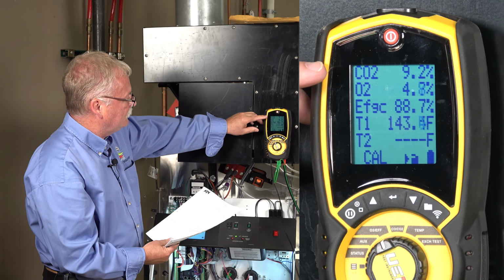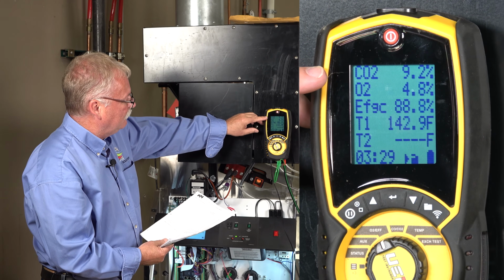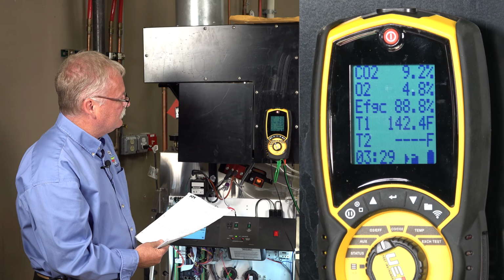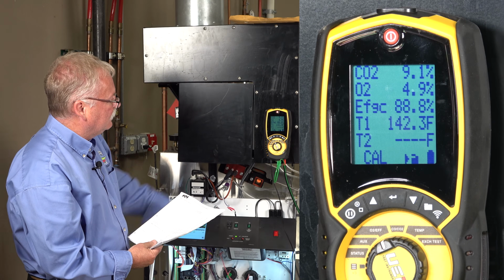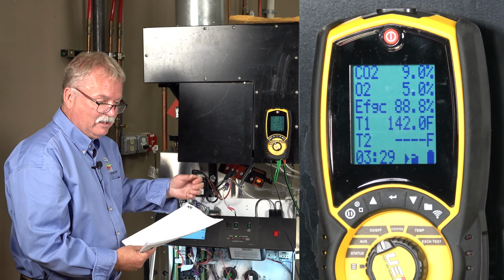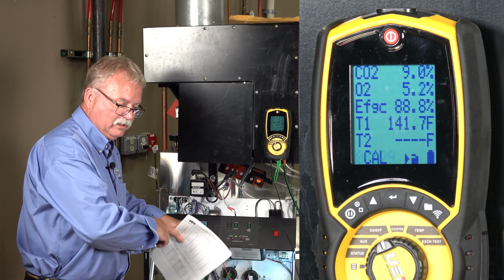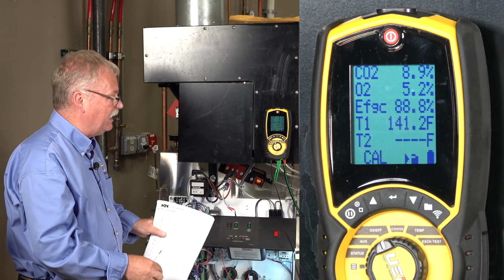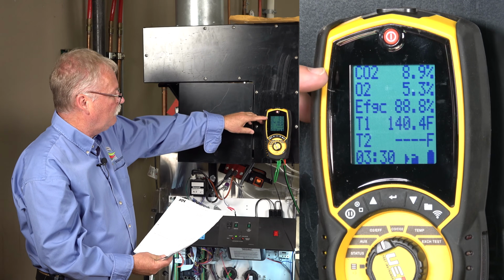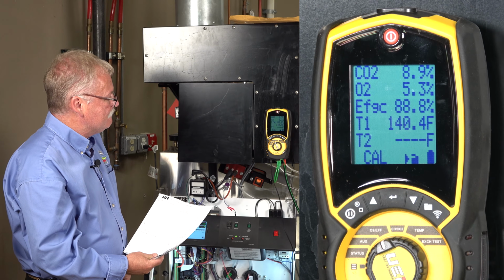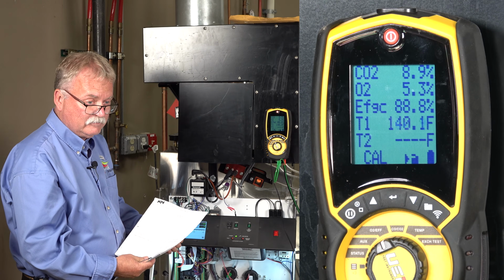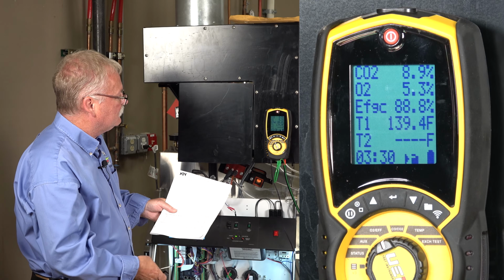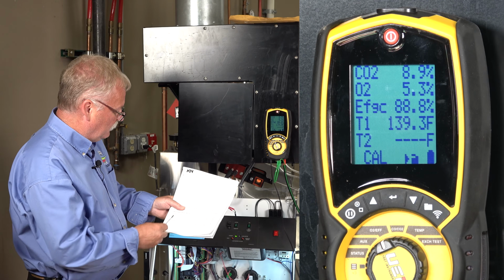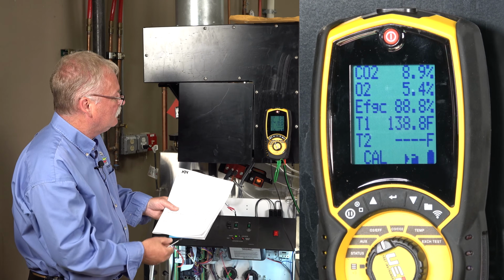What's happened to my CO2? It dropped down a little bit. My efficiency's holding. Drop down another tenth. Again, do not make an adjustment and immediately go somewhere else. Let it settle down. Now we're down to 8.9. And you hear no noise at all. Okay? Not bad. But really I want to get down to this 8.5.